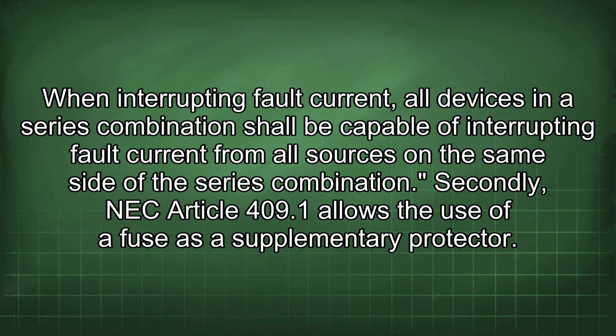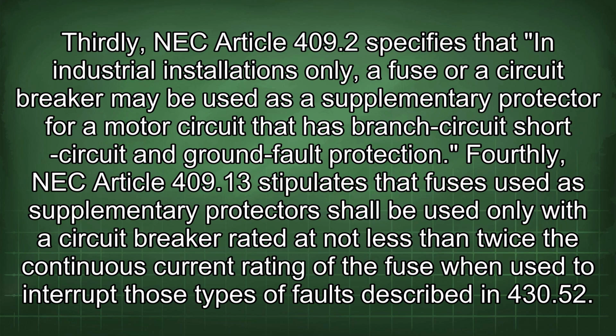When interrupting fault current, all devices in a series combination shall be capable of interrupting fault current from all sources on the same side of the series combination. Secondly, NEC Article 409.1 allows the use of a fuse as a supplementary protector. Thirdly, NEC Article 409.2 specifies that in industrial installations only, a fuse or a circuit breaker may be used as a supplementary protector for a motor circuit that has branch circuit, short circuit, and ground fault protection.